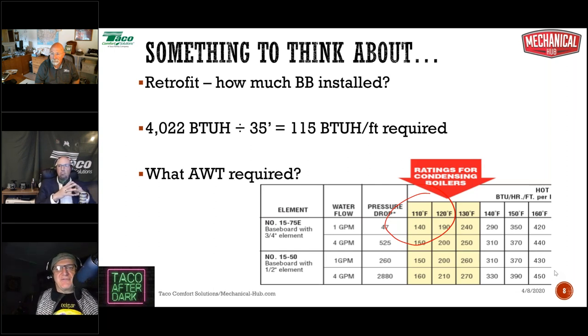You're assuming that the guy 45 years ago did the math all the way so you wouldn't have to, and you're also assuming nothing's changed. So you always want to do a heat load and measure the baseboard. Some folks will just measure the baseboard, multiply by 500, and say that's the heat loss. No, that just tells you how much baseboard is installed. It's good information that we can use, all right? So that's a way to use this information. And if you do a heat loss, once you know the information, you can always use it.